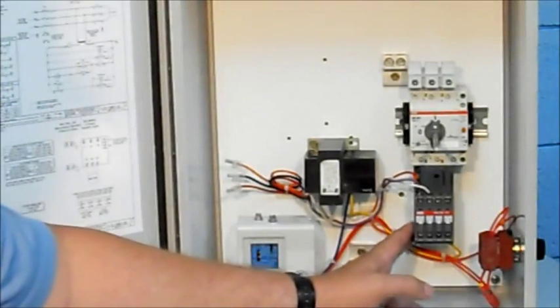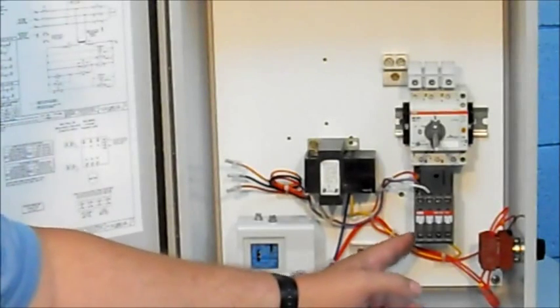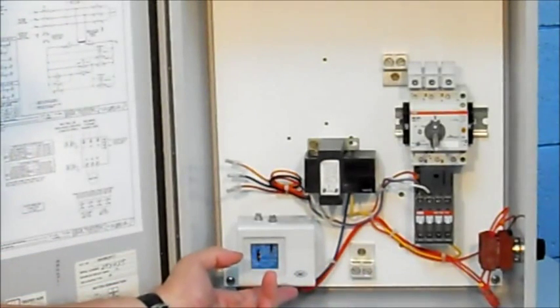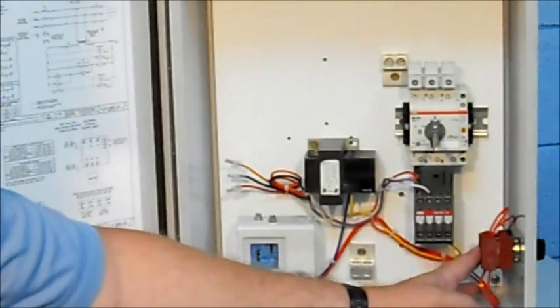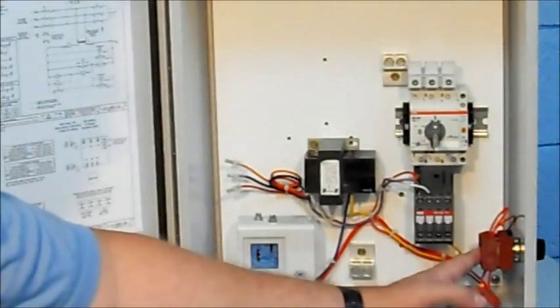Again, in the auto position, if you want the pump to stop before it reaches the upper set point of the pressure switch, just move the selector switch to the off position.